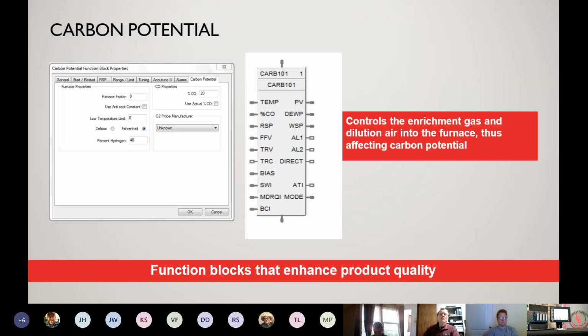As I was talking earlier, there are some standard function blocks right out of the box that you can use. This would be an example of a carbon potential function block that's used a lot in atmosphere enrichment type applications in the heat treat industry. So this is used to control the enrichment gas and the dilution air into the furnace, and that affects your carbon control or your carbon potential that's in that heat treat furnace. So this control loop here would probably mimic a UDC 3200 or 3500 that's using the carbon potential algorithm. And as you double click onto this block, you get an expanded area on the left-hand side where you can then configure that function block.